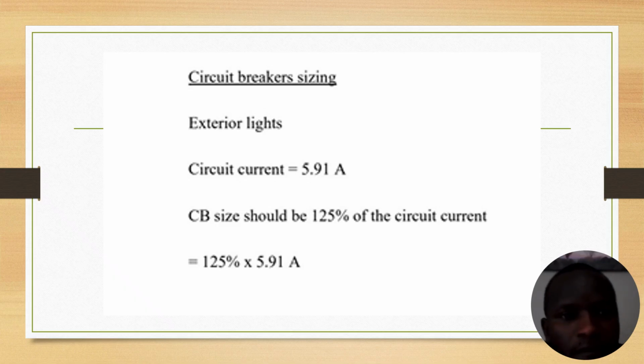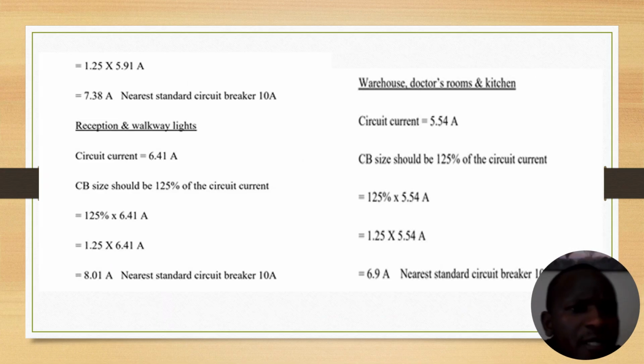The circuit breaker sizing: for the exterior lights, the circuit current will be 5.91 amps. This sizing will be multiplied by 125%, whereby we will get 7.38 amps. Then when we do these calculations for the circuit breakers, we take the nearest standard circuit breaker. For example, where it's 7.38 amps, then we take the nearest, which is 10 amps.